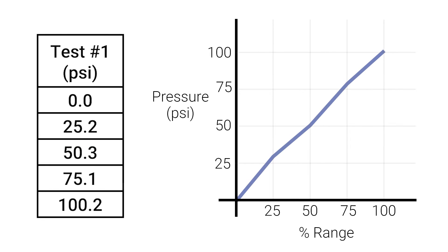When plotted on a graph, these test values will form a line. The closeness of this line to a perfectly straight line is the linearity of the measurement. A calibration curve will be applied to the gauge under test in an attempt to get its readings as linear as possible throughout its testing range.